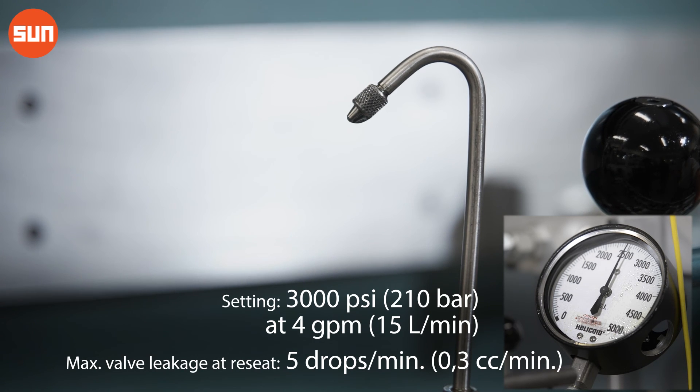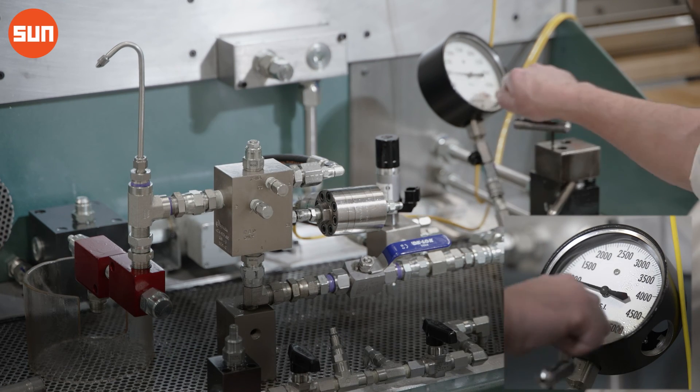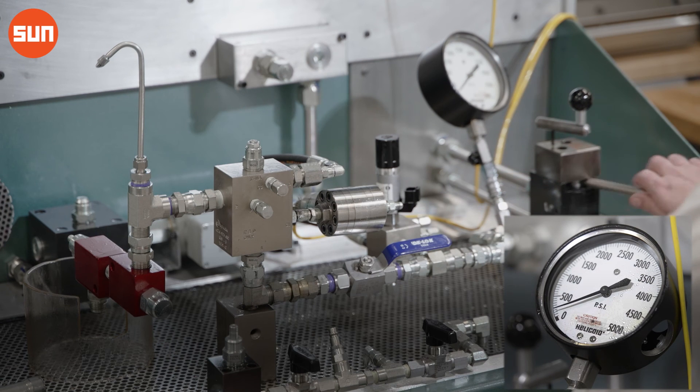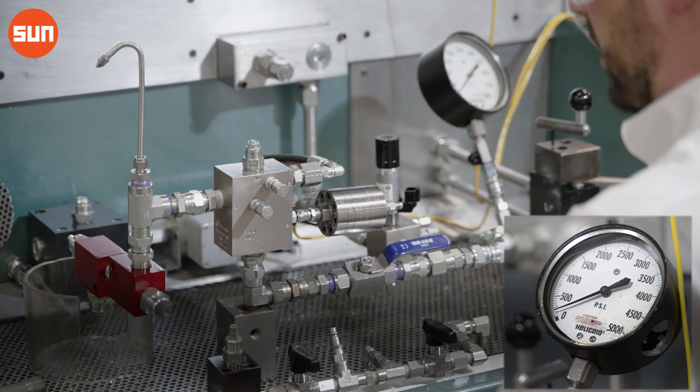Once we've verified that we have less than five drops a minute out of the p-tube, we can take our test stand pressure down to zero, shut the stand off, and our counterbalance valve is set.